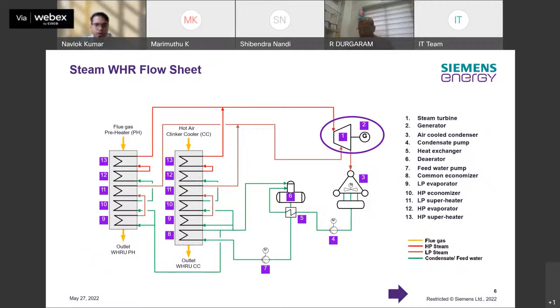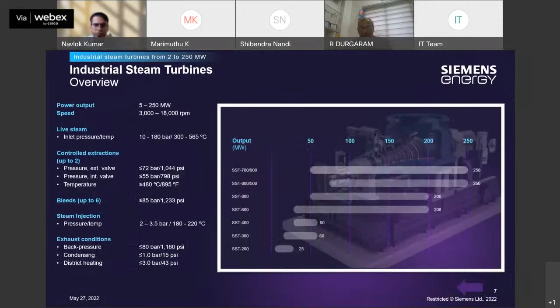Let us have a closer look at our steam turbine offering. Our product portfolio in industrial steam turbine offers a wide product range. The capacities range from 2 megawatt to 250 megawatt. The RPM of these machines varies from as low as 3,000 to as high as 18,000 RPM. The main steam inlet pressure ranges from 10 bar to 180 bar. The injection steam pressure ranges from 2 bar to 3.5 bar. These turbines are manufactured at our state-of-art manufacturing facility in Vadodara plant, Gujarat, India.